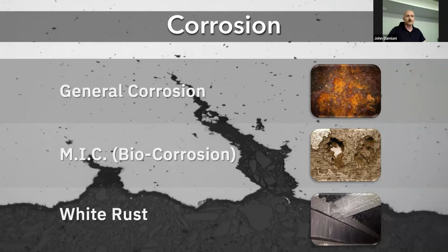We're slowing corrosion down as much as possible using technology, equipment, and chemistry. Biocorrosion has a similar result to general corrosion, but is specific to corrosion occurring as a result of sludge and biofilms forming, because bacteria and biological microorganisms produce waste that can be acidic, and underneath the biofilm you can have active corrosion. The problem is your corrosion inhibitors, even added at the correct rate, aren't reaching that part of the metal because it's protected and covered by the biofilm, so the bacteria is actually protecting itself and causing pretty rapid corrosion underneath.